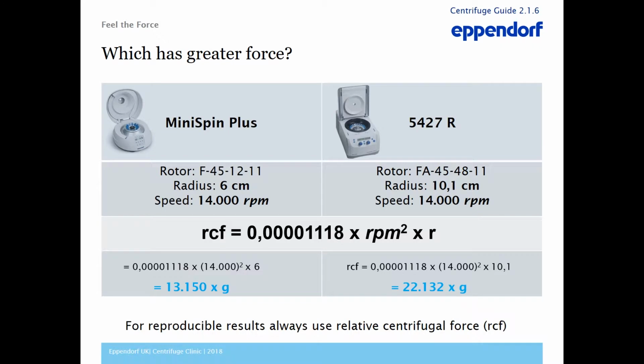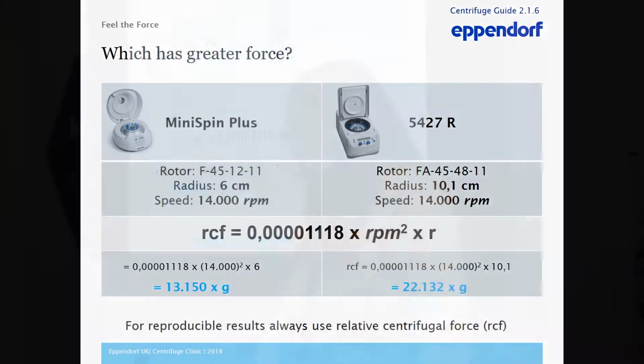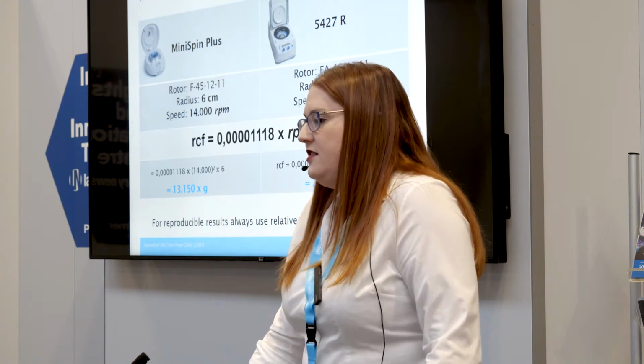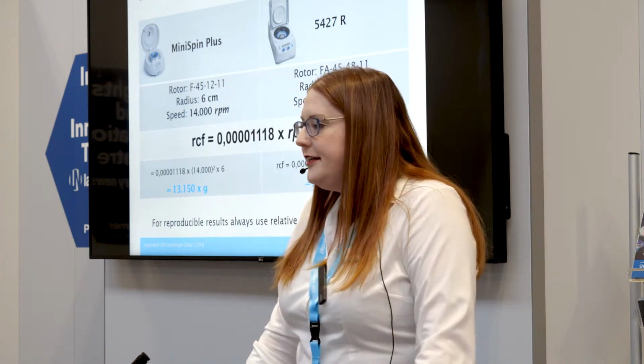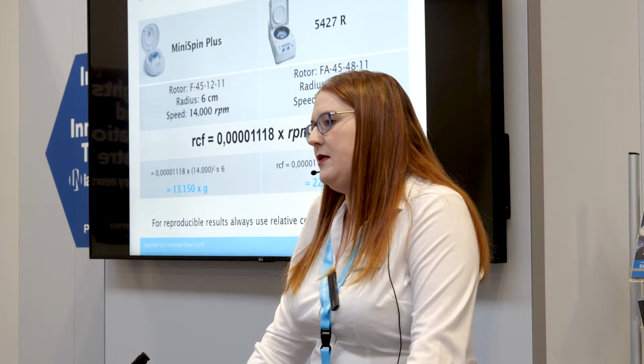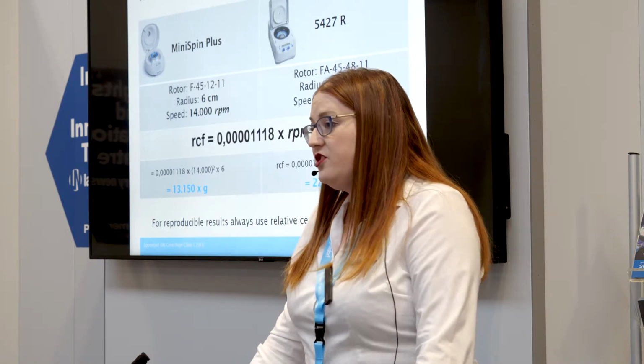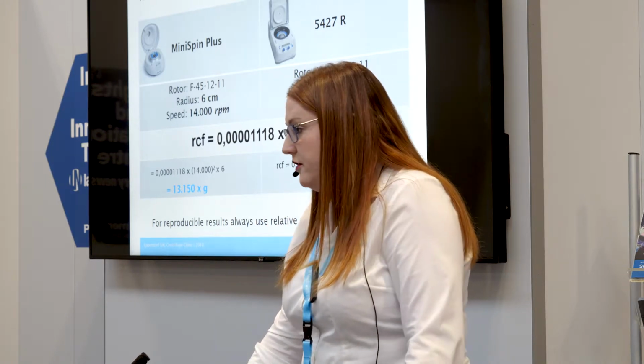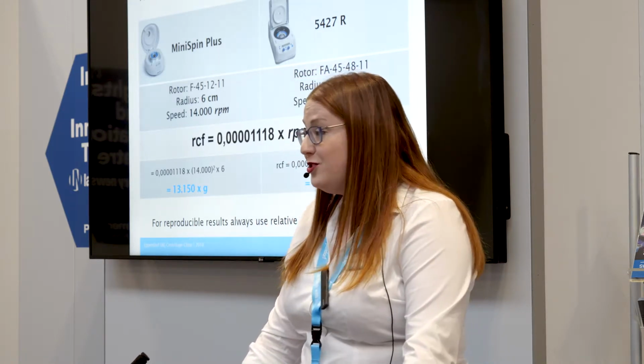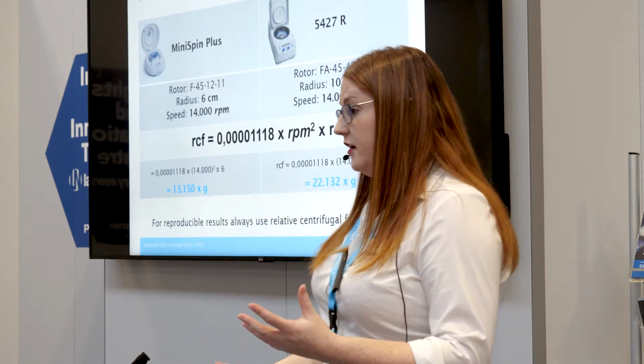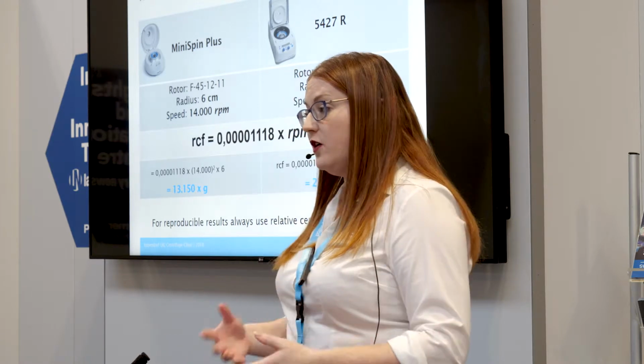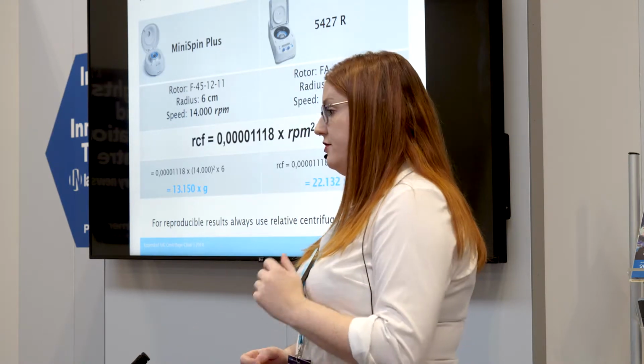Now, we always say for reproducible results, use centrifugal force. This is also relevant if you're purchasing a new centrifuge. I am regularly asked for a centrifuge that can spin at 3,000 RPM, which is great. What were you spinning before? Because 3,000 RPM in one centrifuge is very different in a different centrifuge. And most people don't know, which means I have to work it out for them. Which is fine, but it means that your results are not going to be reproducible as soon as you swap centrifuge.